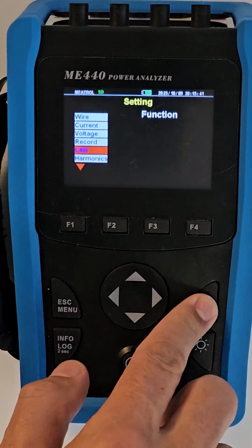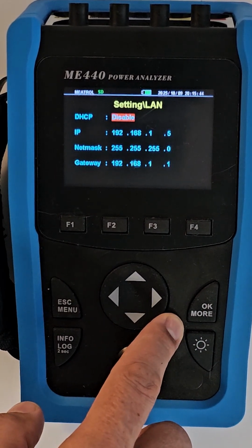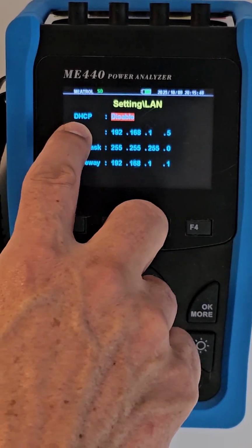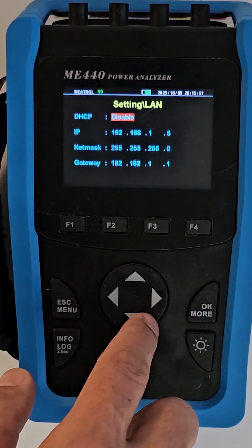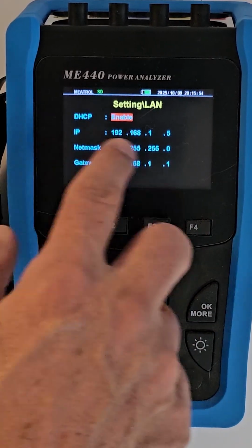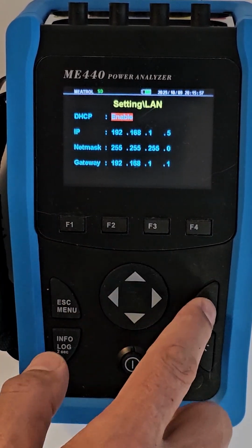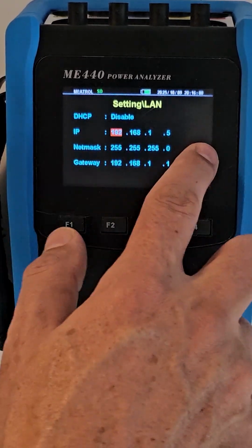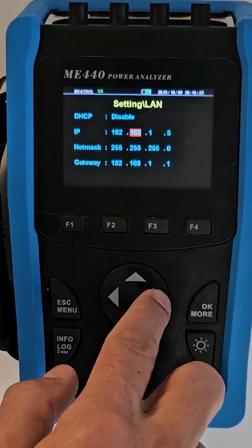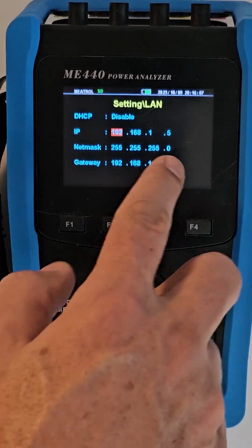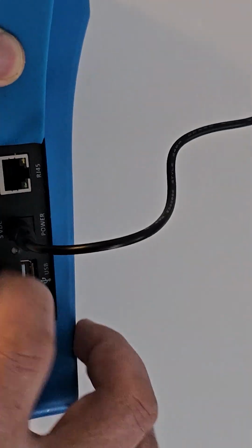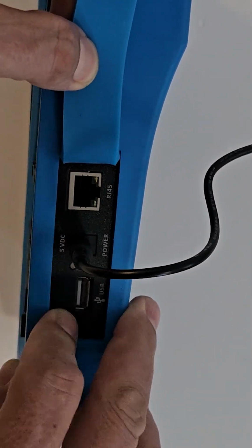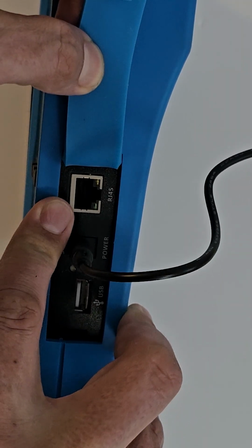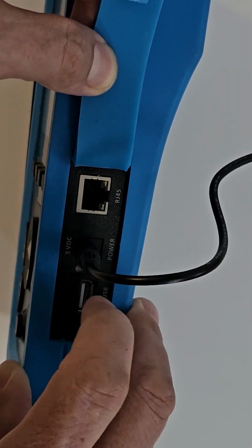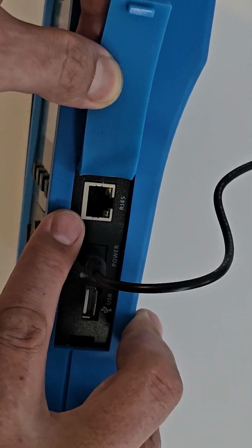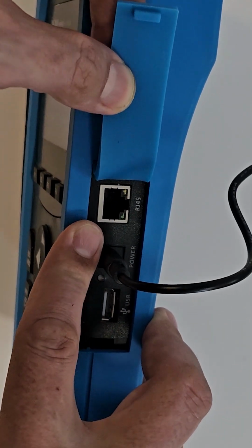Okay, so you move on to the LAN menu. Here you can set the IP address, either to be assigned automatically by DHCP, Dynamic Host Configuration Protocol, or to be assigned manually. So you can enable or disable DHCP here. And then you can set your IP address, net mask and gateway address. Quite normally the default address is 5, and on the side here you'll see there's an RJ45 LAN port, and it uses Modbus over Ethernet to communicate to the meter. There's a software application that can communicate to the meter, or you can also use gateways to access the data that the meter records.